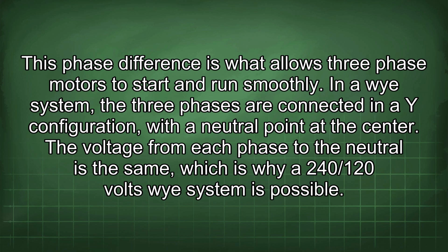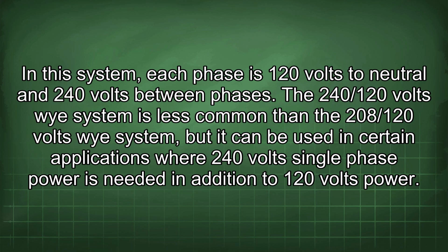In a Y system, the 3 phases are connected in a Y configuration, with the neutral point at the center. The voltage from each phase to the neutral is the same, which is why a 240/120 volts Y system is possible. In this system, each phase is 120 volts to neutral and 240 volts between phases. The 240/120 volts Y system is less common than the 208/120 volts Y system, but it can be used in certain applications where 240 volt single-phase power is needed in addition to 120 volts power.